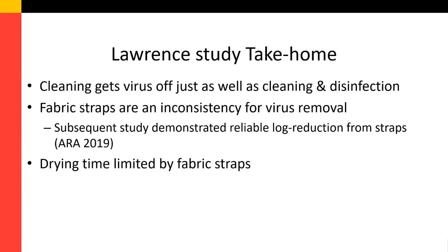So the take home from this Lawrence study is that cleaning gets virus off just as well as cleaning and disinfection in this study where influenza was tested. The fabric straps may be an inconsistency for virus removal, but again, this subsequent study demonstrated reliable log reduction from the straps, and that drying time on the elastomeric respirators is limited by the fabric straps.